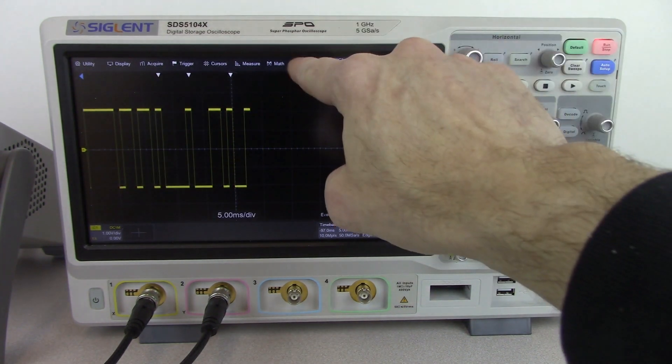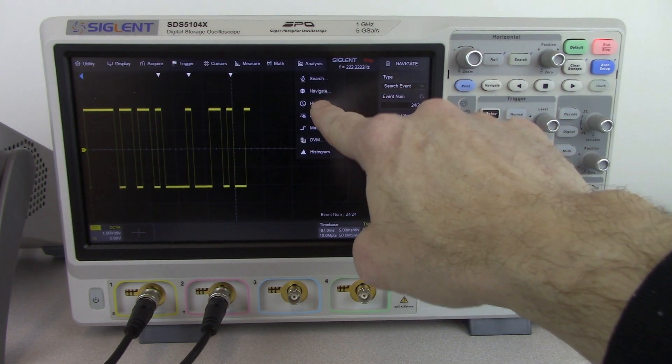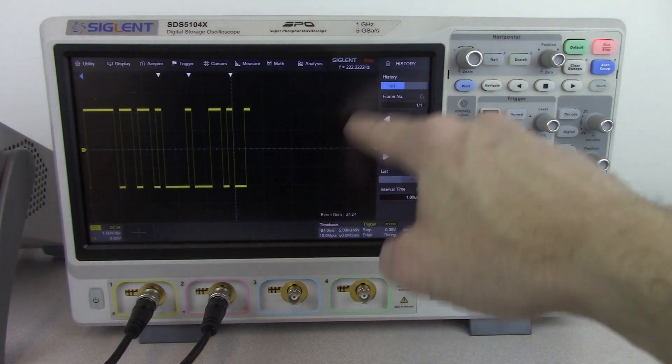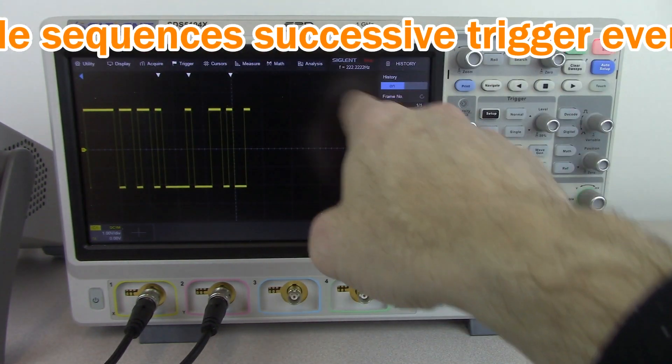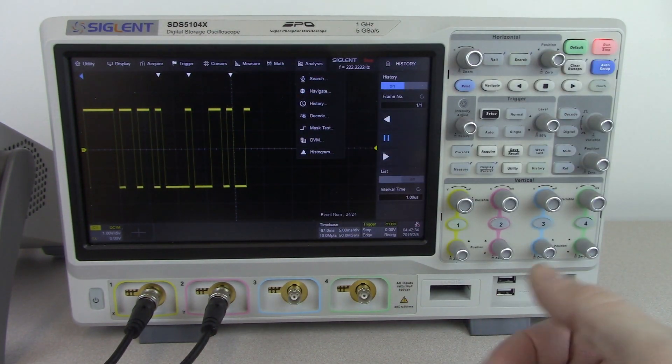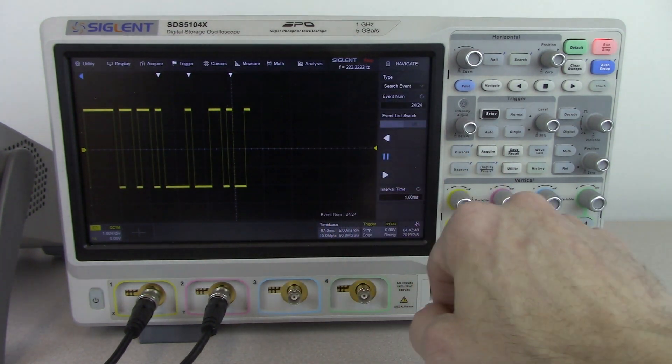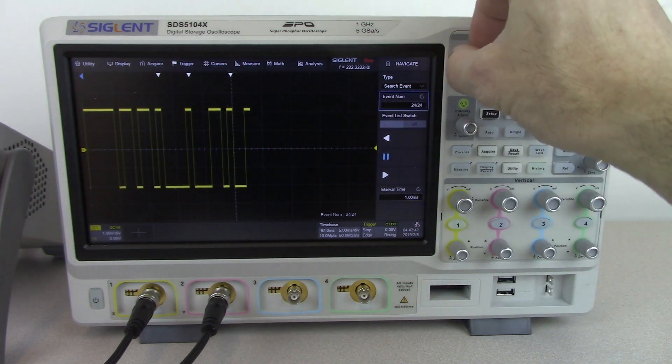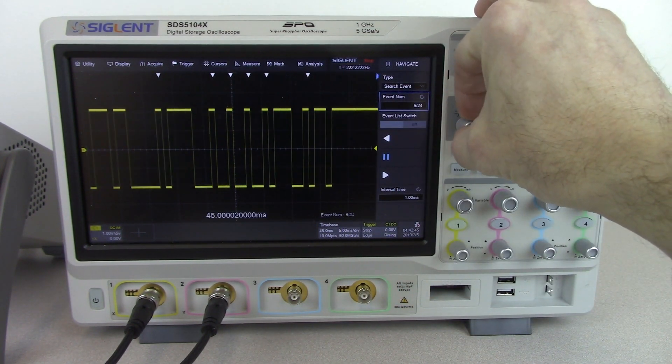We also have, similar to the search event, a history function. The history function is going to take successive frames of data and show those individual frames very much like a movie. We also have the ability to perform mask tests. We can set up a mask on the display and it can give us a pass or fail. We can also take a look at the navigate and pop through different events and be able to search through each of those.